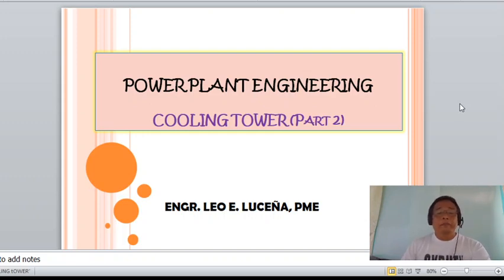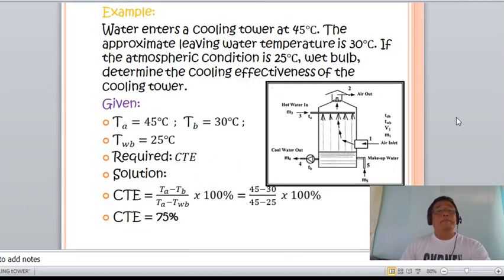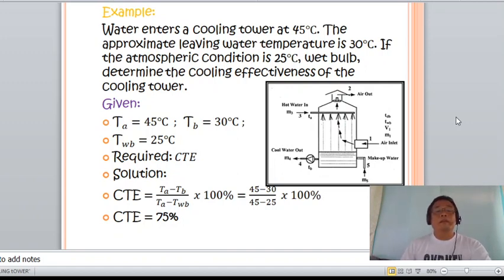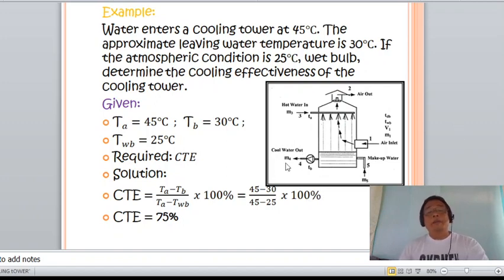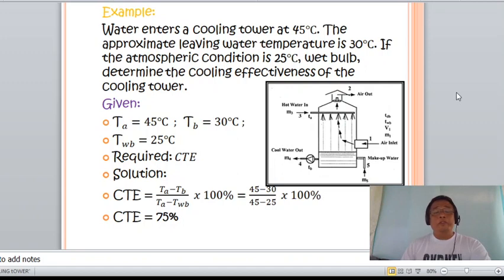Let us consider this problem: water enters a cooling tower at 45 degrees Celsius, the approximate leaving water temperature is 30 degrees Celsius, and the atmospheric condition is 25 degrees wet bulb. Determine the cooling effectiveness of the cooling tower. Let us now break down the given: the temperature of water entering the tower is 45°C, the wet bulb temperature of air entering the tower is 25°C, and the temperature of the cold water is 30°C.